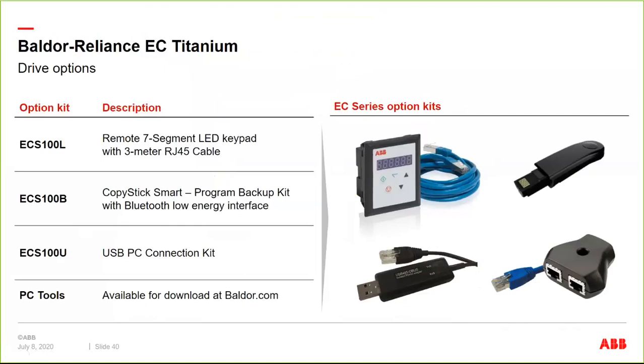the unit. Being an RS-485, a standard serial interface, you can also daisy chain the keypads together, or have one keypad and then a splitter going to multiple drives, and then you can just do node assignments. So let's say you had a fan array and you had 12 fans on that. You could connect them all serially together with the splitter and have one keypad, and then just select which node you want and look at the drive.